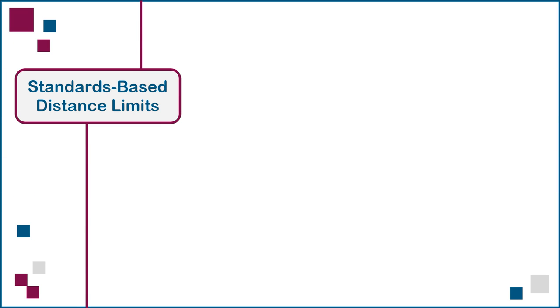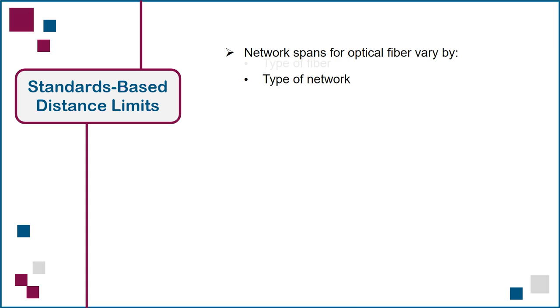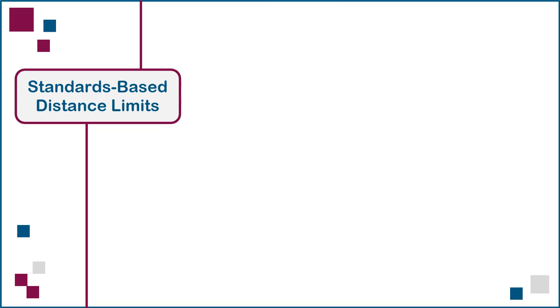Next, we'll review the standards-based distance limits for optical fiber cabling channels, which vary by both network type as well as by type of fiber used. Unlike twisted pair copper cabling systems with their well-established 100-meter maximum channel length, the network spans for optical fiber vary by type of network, type of fiber, and even by the wavelength used over a given type of fiber. The designer must therefore match the capabilities of the proposed fiber links to the requirements for current and future network implementations.